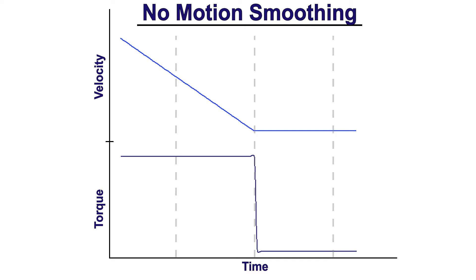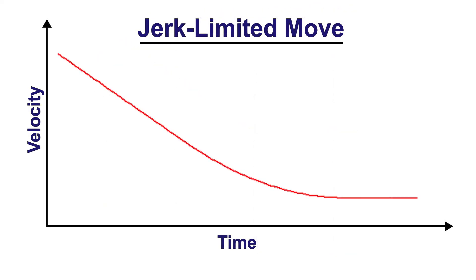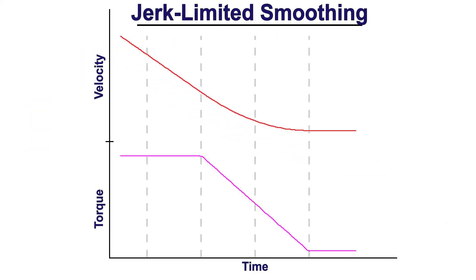With a standard trap move and no smoothing applied, the motion and torque response look very abrupt and rough - definitely not mechanically friendly. This is why most servo systems have some sort of smoothing algorithm, whether cosine smoothing or S-curving, to make the motion profile less abrupt. Let's look at the trapezoidal move with the first degree of smoothing, which is jerk-limited smoothing. Looking at the same point in the profile where we're going from deceleration to zero velocity, the motion profile itself looks much smoother. The corner before the endpoint is curved rather than sharp, but the proof is really going to be in the torque domain.